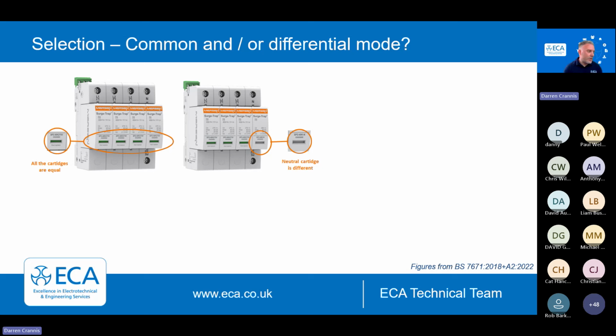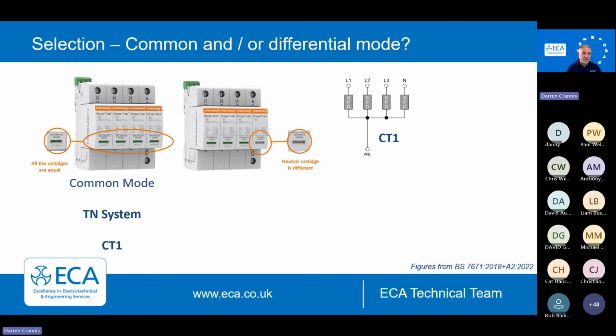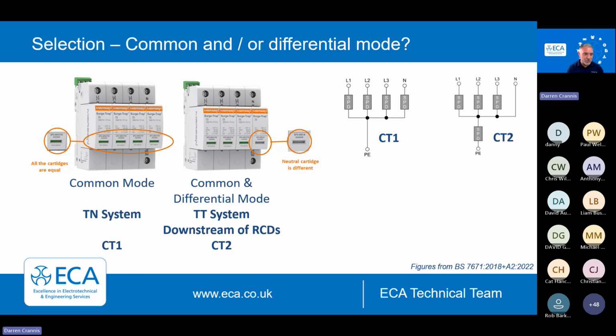We briefly covered this with RCDs, but there are a couple of variants of SPD, common or differential mode, and why do they differ? Common mode is CT1, and what you'll see here predominantly is that this is for TN systems. Often it will say suitable for TN-S or TN systems. This is because the neutral is actually connected to earth with a metal oxide varistor, and there is a slight leakage through that. So with TT installations and RCDs, that would cause a tripping issue. It's the last thing you want on a Friday afternoon.